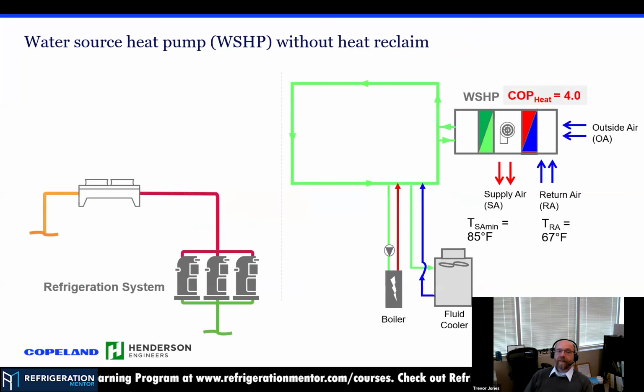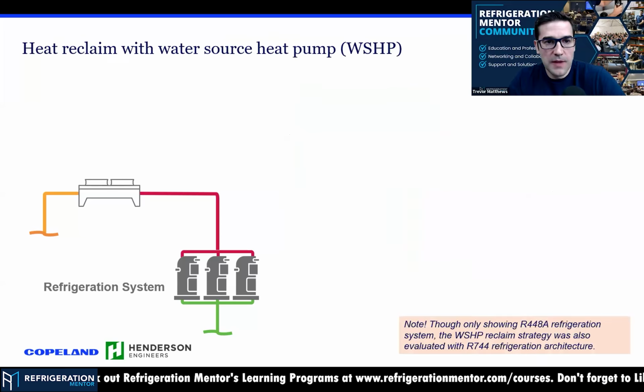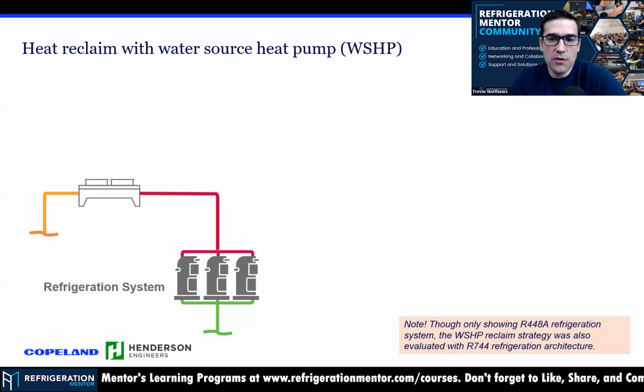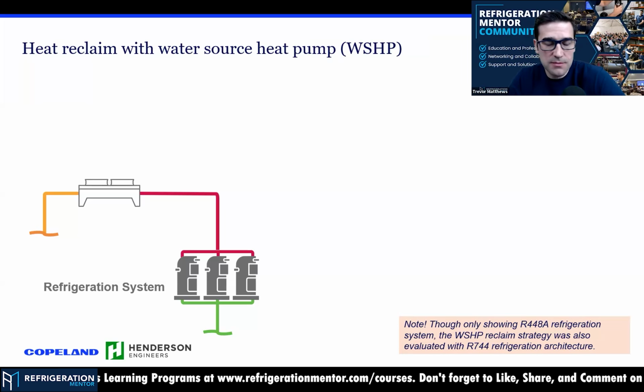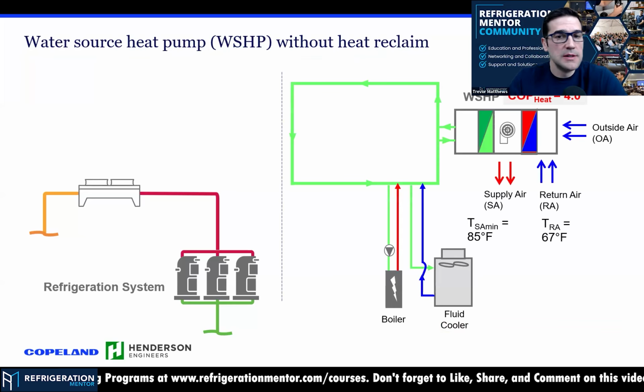We also looked at, without reclaim, the water source heat pump system. This is a very simplified water source heat pump schematic, where you'll have a boiler, a fluid cooler for rejecting heat, a boiler to add heat, and a water source heat pump that's just moving heat in and out of the loop as needed. Yeah, it's pretty normal, this is not anything new. If you've worked on some of these before or on a supermarket that has them, there's lots of them out there.